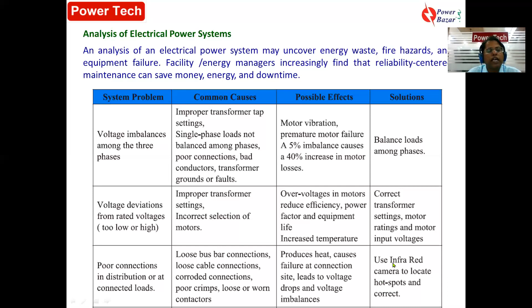Now, if the terminal box shows that it is red hot, that means there is some sparking in a particular phase. So you have to open the terminal box and tighten. Undersized conductor means your resistance will be higher, your design will not be good, there will be poor power factor, voltage drop, and energy wastage. So what you have to do? You have to either reduce the load or increase the conductor size.